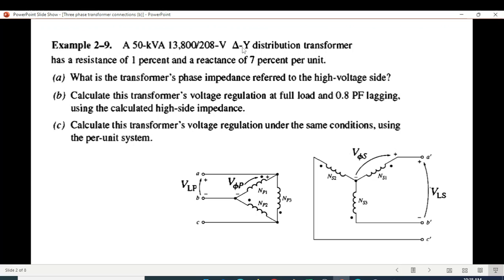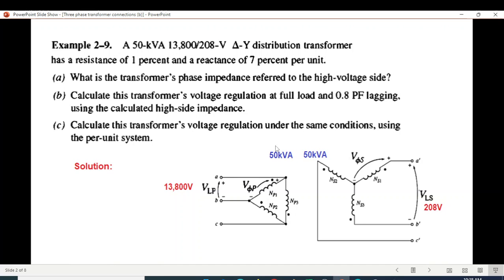First, delta-Y distribution transformer, we can draw this: primary side delta, secondary Y connection. We can input the data. Power: 50 kVA on both sides. Primary power 50 kVA, secondary power also 50 kVA. Input voltage is line-to-line voltage, so 13,800 volt line-to-line voltage between line A and B, between B and C. Secondary line-to-line voltage: 208 volt, secondary voltage 208 volt.